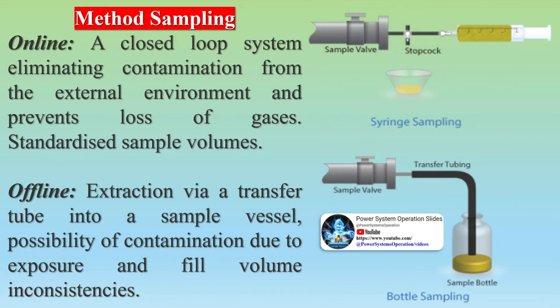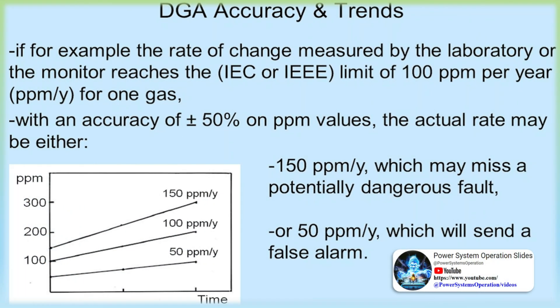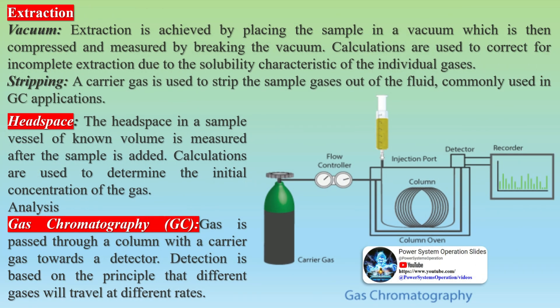Regarding sampling methods: online sampling uses a closed-loop system eliminating contamination from the external environment and prevents loss of gases, with standardized sample volumes. Offline sampling involves extraction via a transfer tube into a sample vessel, with the possibility of contamination due to exposure and fill volume inconsistencies. Extraction methods include vacuum extraction, where the sample is placed in a vacuum then compressed and measured; carrier gas stripping commonly used in GC applications; and headspace measurement, where the headspace in a sample vessel of known volume is measured after the sample is added.